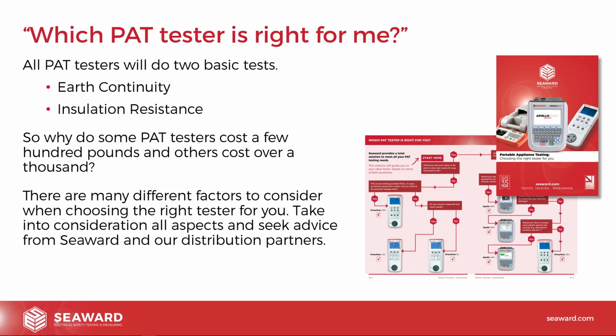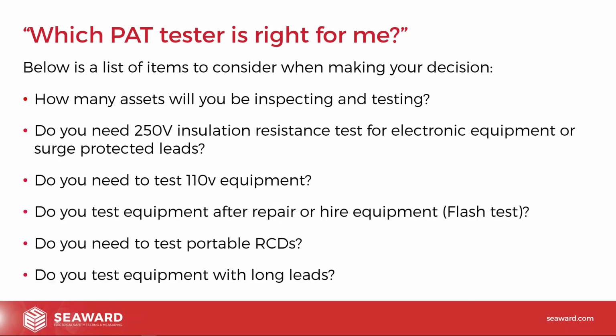So as it says on the slide, most PAT testers, or all PAT testers, will do earth continuity and insulation. So why do some cost a few £100s and some cost over £1,000? This is really what we're going to talk about now. There are loads of things you need to consider when you're doing PAT testing. We mentioned how many assets you have actually got. Do you need to be able to do a 250 volt test? So have you got sensitive equipment? Have you got surge protected equipment? Do you need to do a 110 volt test? Or do you need to be able to test 110 volt equipment?